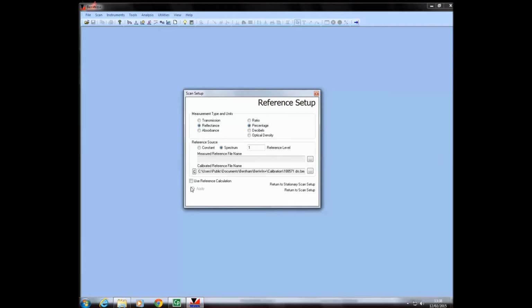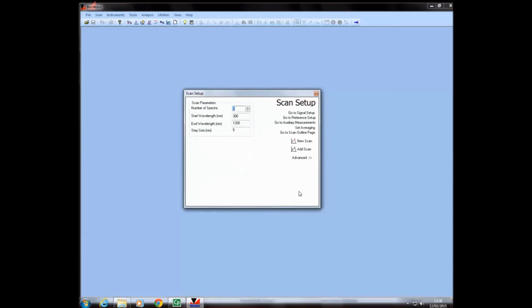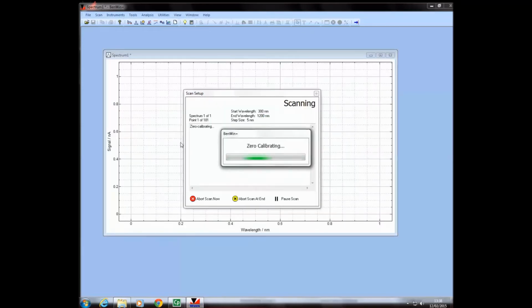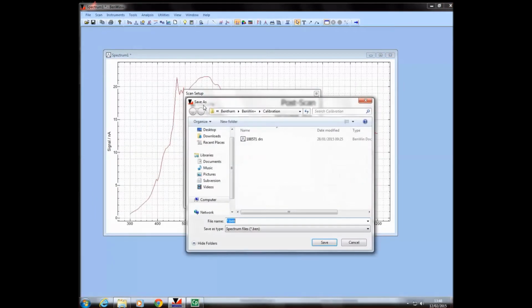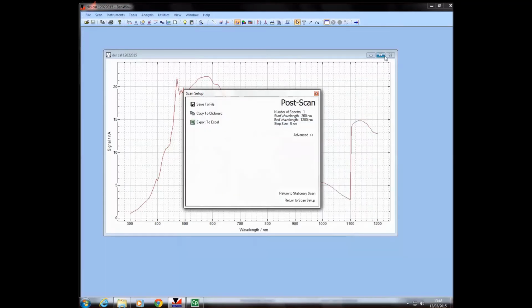For now we are performing the reference measurement for the spectral reflectance measurement, so use reference calculation should be switched off. We will perform a scan over the same range over which we have performed the spectral responsivity measurement, 300 to 1200 nanometers, and hit new scan. At all times, when determining the reference levels, signal in nanoamps should be displayed on the y-axis. We can save this measurement to file in the spectral folder. This is the DRS calibration, and today is the 12th, 2015. I can close that file.